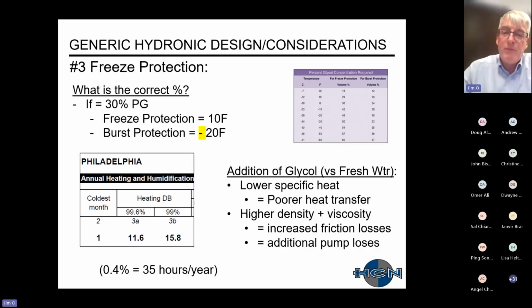Just realize that when you add glycol versus fresh water, the glycol has a lower specific heat than water, so you have poorer heat transfer. In addition, the glycol is more syrupy, so it has a higher density and viscosity. What ends up happening is you get additional losses through your pump, and increased friction losses through your piping and coils.